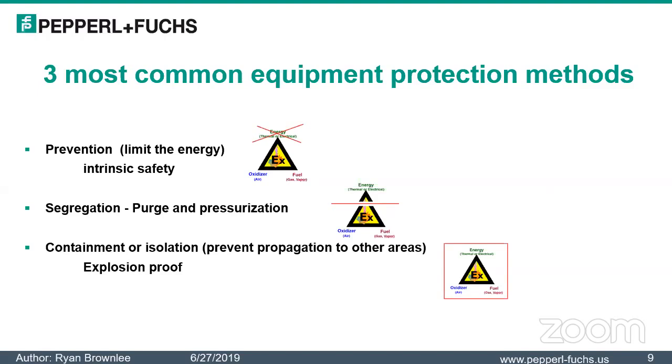It's all bolted and closed up. This is sort of a general purpose location in this box. Okay, so if something happens, we're going to contain it. It will get out of here, but because of the design of the enclosure, you get a refrigerant effect. The bolts are tightened down. So what happens is the burning gas gets cooled. So if the gas exits the enclosure at 399 degrees, and whatever I have in the environment is at 400 degrees, I'm not going to have an explosion because the gas is not hot enough to ignite an event. Okay? So we'll cover these in a little more detail.